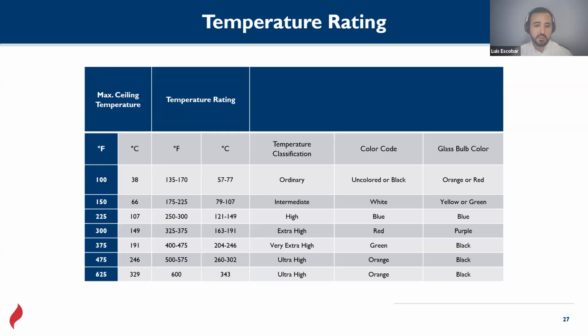So different colors mean different temperatures of activation for different applications. It's not going to be the same to have a sprinkler on a ceiling for a manufacturing plant or a metal extruding plant than a break room, for example. Obviously, the break room will have air conditioning. It's going to be, I don't know, 75 degrees at all times when it's air conditioning controlled. And when there's a fire, the temperature starts going up until we hit this value. Then the bulb breaks and the water starts to extinguish the fire. And the same for all these.